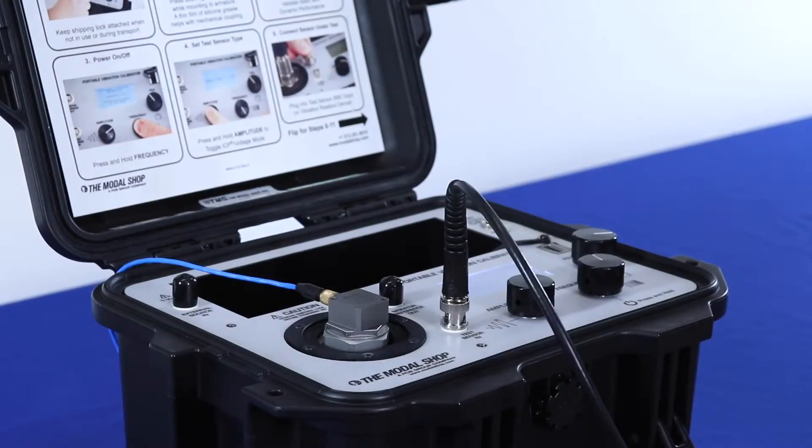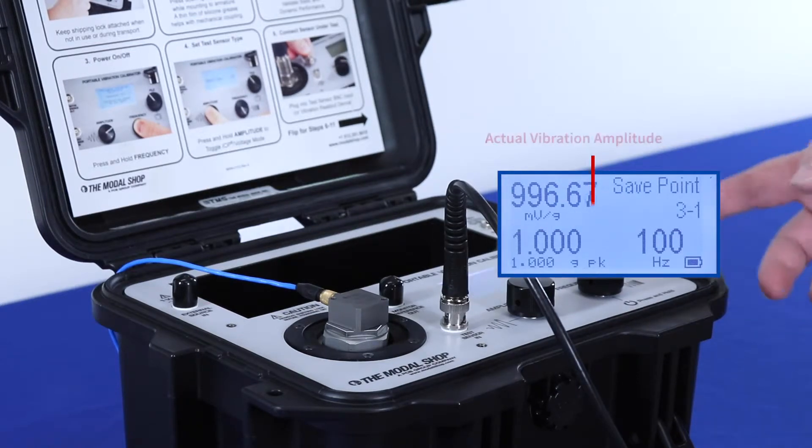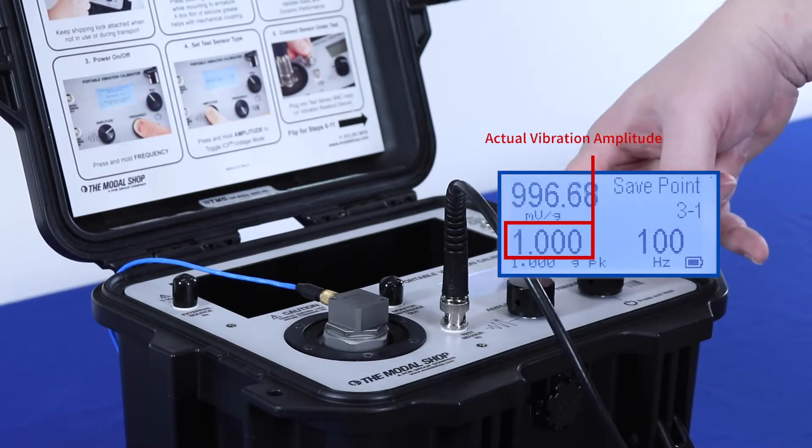We're going to calibrate this PCB Piezotronics 1000 mV per G DC MEMS accelerometer at 6 points, beginning at 100 Hz and ending at 1 Hz. You can see here that the sensitivity of the sensor under test is 996 mV per G at 100 Hz.